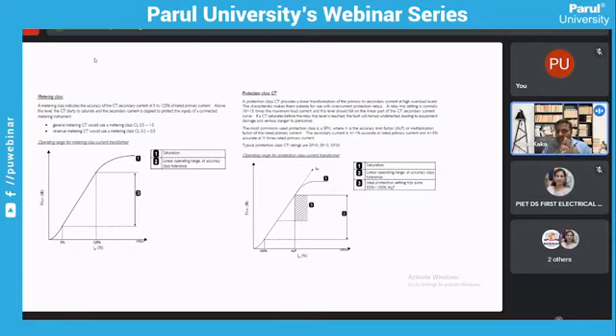Now again, the protection class CT, we all know that it will be defined as 5P10, 5P15, and 5P20. This is something like accuracy limit factors and how much the CT can transform without getting saturated. So, protection class CT provides linear transformation of the primary to secondary current at higher overload levels. The characteristics make them used for overcurrent protection. Normally, the relay trip settings are set for 10 to 15 times the maximum load current. This level should fall near the linear part of the secondary current.